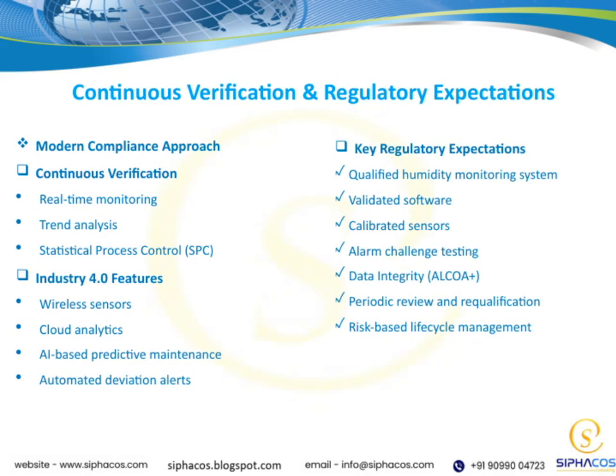When it comes to regulatory expectations, there are several key elements we need to keep front and center. We're talking about qualified humidity monitoring systems, validated software, and calibrated sensors. Alarm challenge testing is crucial, along with strict data integrity following ALCOA plus principles. Plus, periodic review and requalification ensure ongoing compliance, all within a risk-based lifecycle management framework. On the continuous verification side, real-time monitoring, trend analysis, and statistical process control help us stay ahead. Industry 4.0 brings wireless sensors, cloud analytics, AI-driven predictive maintenance, and automated alerts, all designed to make compliance smarter and more proactive.